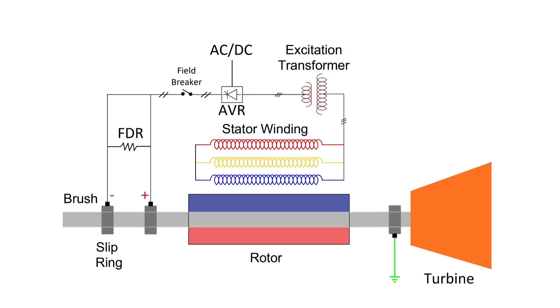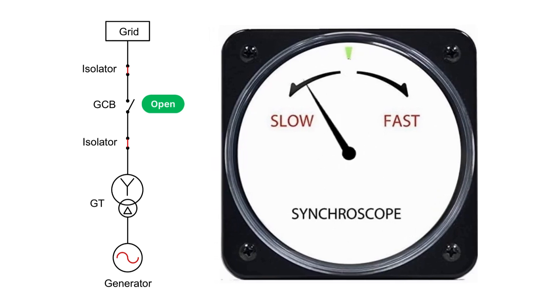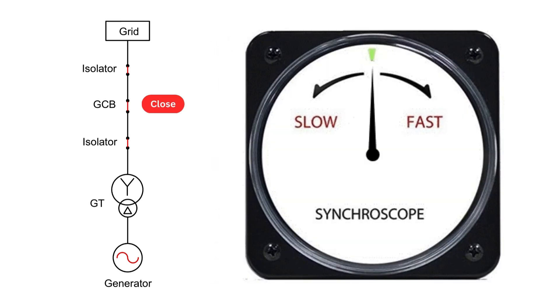The turbine is rolled at 3000 rpm to achieve 50 Hz frequency and the excitation voltage is adjusted to match the grid voltage. If the turbine speed is increased slightly, the synchroscope will rotate in the fast direction. When the needle reaches the 12 o'clock position, the operator closes the GCB to synchronize the generator with the grid.